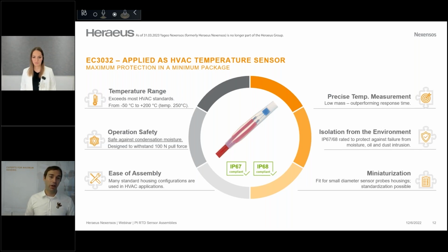I think you could follow on the temperature sensor. This is the EC3032. Charlotte, you talked about this one. We wrote here maximum protection in the minimum package, and the idea was for HVAC applications. In HVAC applications, a lot of times you have the challenge that you have condensation, moisture potentially creeping into the sensor area and harming the performance over time. So the construction that you see here in the middle looks very simple. It's a polymer flexible tip, but it's highly dense. It has a low thermal mass, so very good response time. And we approved it as IP67 and IP68 compliant. So it really performs really well if you have a wet environment, if there's moisture, if there's dust, if there's vibration.